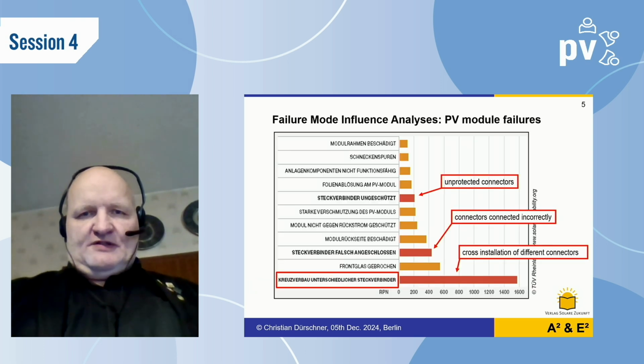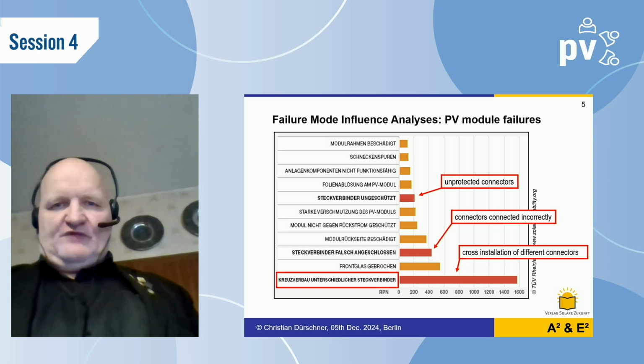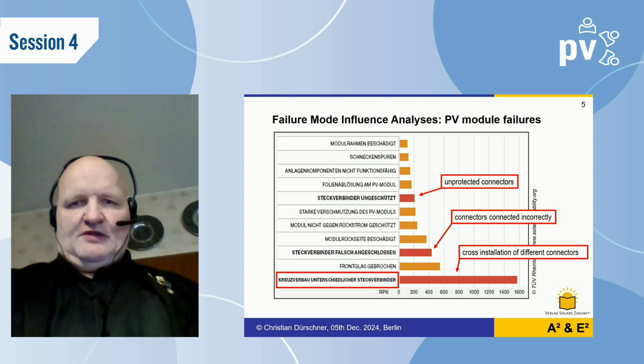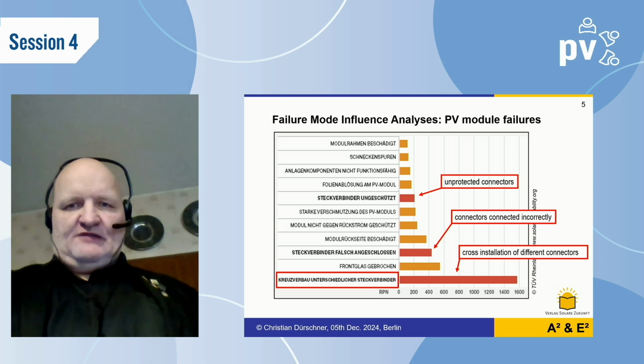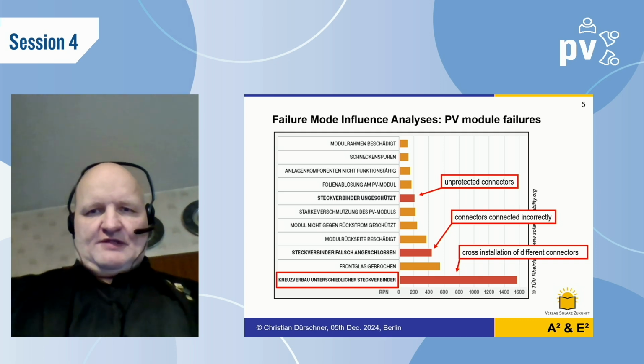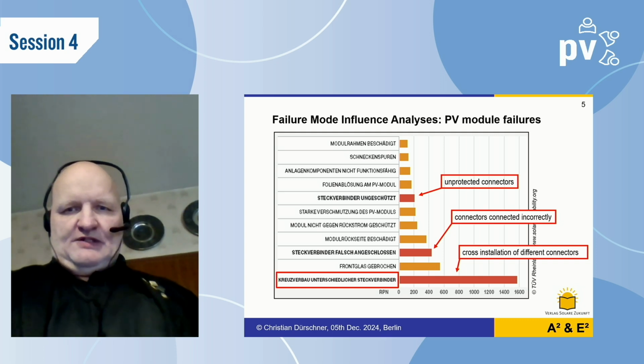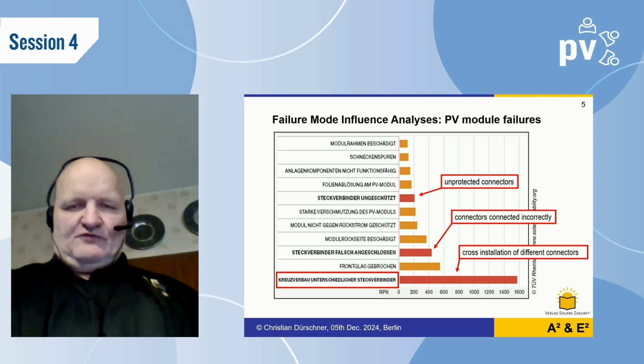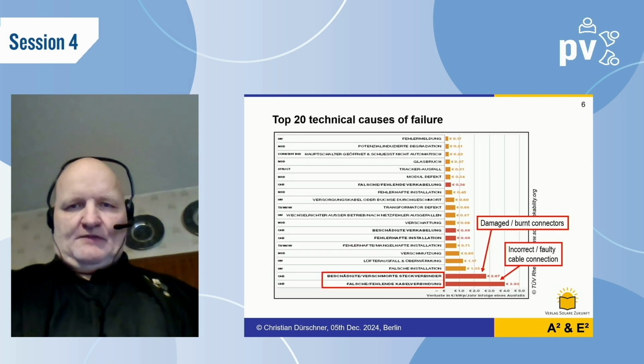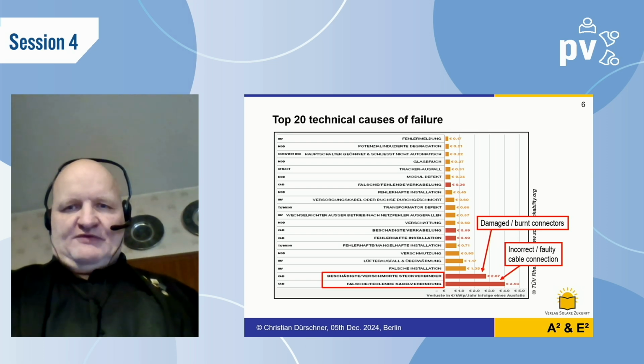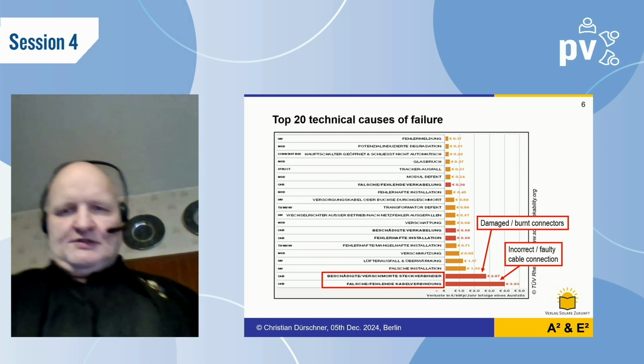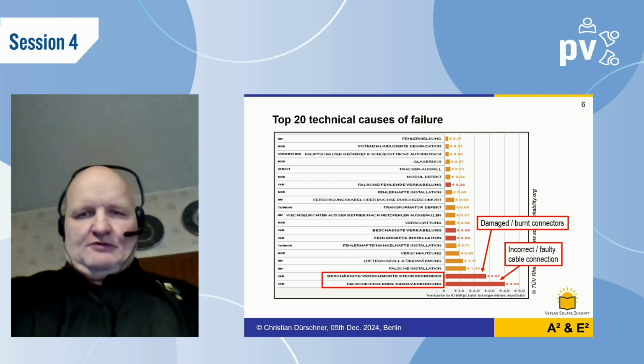There are several investigations. Here is one failure mode influence analysis of PV module failures. You see a lot of failures, but three times here it shows issues with connectors and cabling, and you really lose a lot of money going wrong here. Another slide shows this too. I've highlighted both things: damages on burned connections and damages from wrong cabling are really the main issue.